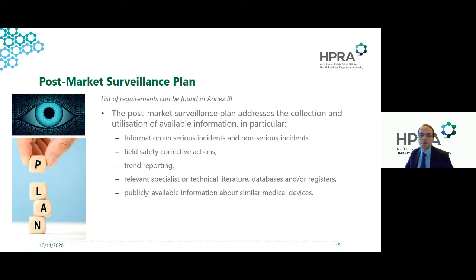In particular, you'd have the likes of serious incidents or non-serious incidents, field safety corrective actions, trend reporting, and relevant specialist or technical literature. So the requirement for post-market surveillance is there already, but you can utilize this to really assist when you're collecting information to update your clinical evidence.